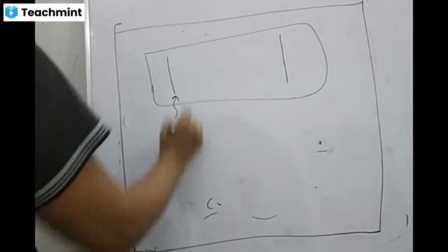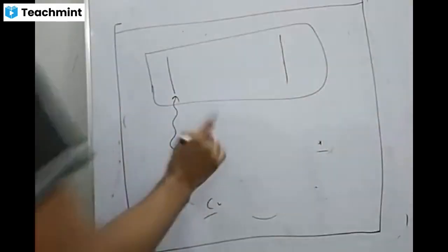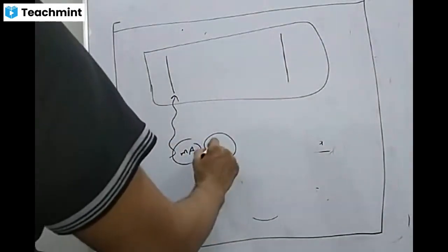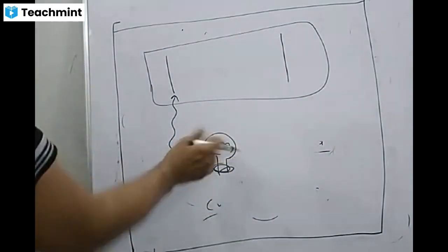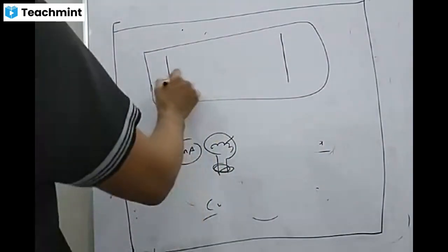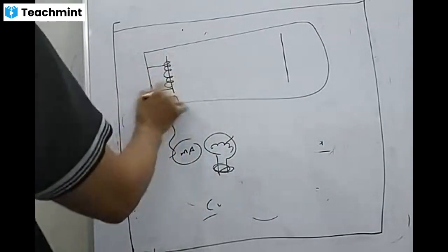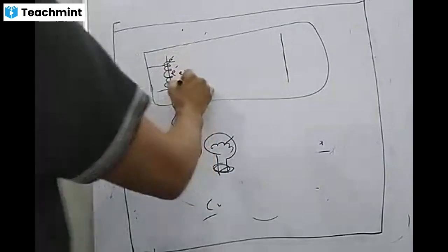We have also entered inside the tube: this is our X-ray tube, with cathode and anode. At this level, we are giving milliampere current. Because of this current, similar to our home bulb, when we switch on, the filament of the cathode becomes heated up. Because of this heating, electrons come out.